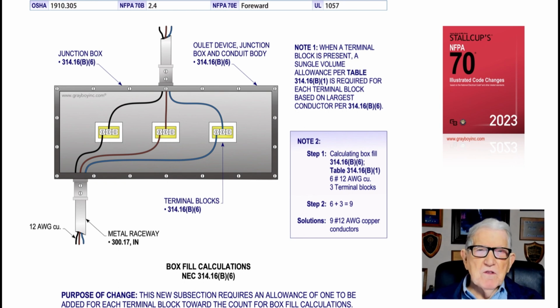And the purpose of the change mainly is for each terminal block that you see in the illustration, you have an allowance of 1 for each. And in note 2, right next to the equipment there, you see that we do the math for you, and the solution says you have to look at 9 number 12 copper conductors. And of course, note 1 tells it all.